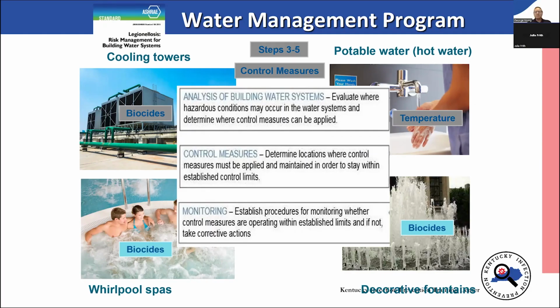Decorative fountains—biocides are the main control you have there. The reason is, especially for an outdoor decorative fountain or an indoor one, like a water wall, the ambient temperature will cause the water being maintained in there to get close to grow ranges. Typically they're only supplied with cold water, so that wouldn't be an issue. But if they have lights in them or they're outdoors, they'll be exposed to temperatures that help that water stay in that grow range. So you'll need some sort of biocide associated with them.